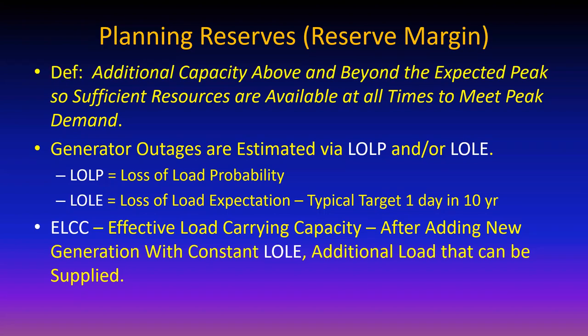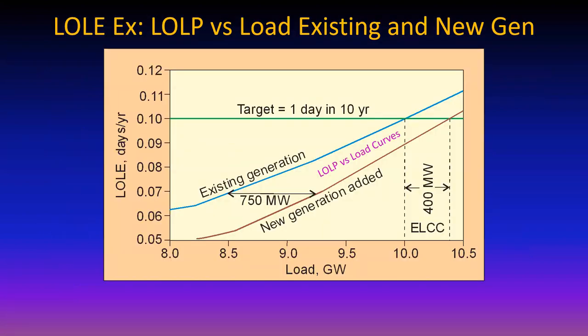So we've got three nice new acronyms, so now we can draw a picture. The picture plots the loss of load expectation versus the loss of load probability versus the existing and new generation. Let's take a look at the blue curve - that's the LOLE versus load for the existing generation. Notice that at 10 gigawatts, the loss of load expectation is 0.1 day per year, which is one day in 10 years, okay?